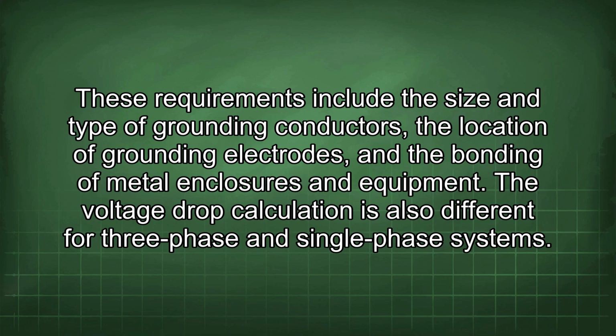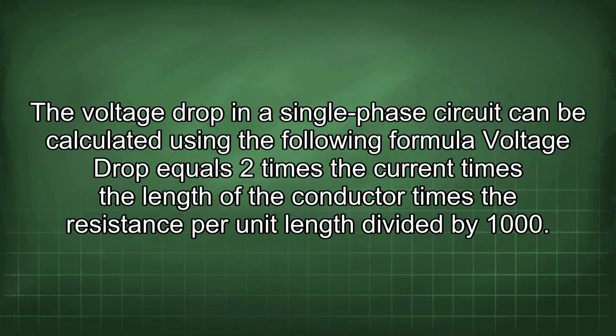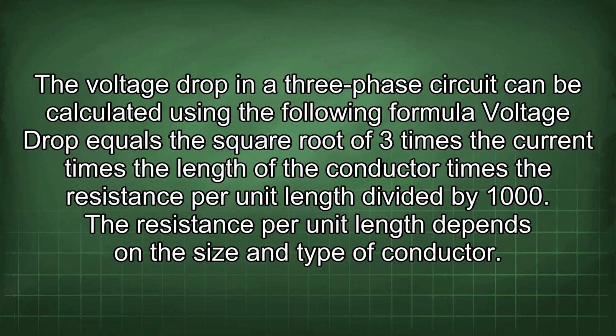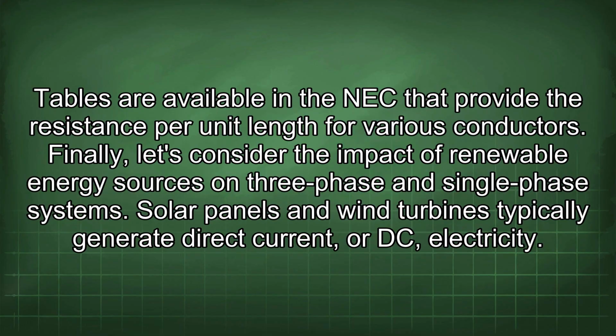The voltage drop calculation is also different for three-phase and single-phase systems. The voltage drop in a single-phase circuit can be calculated using the following formula: voltage drop equals 2 times the current times the length of the conductor times the resistance per unit length divided by 1000. The voltage drop in a three-phase circuit can be calculated using the following formula: voltage drop equals the square root of 3 times the current times the length of the conductor times the resistance per unit length divided by 1000. The resistance per unit length depends on the size and type of conductor. Tables are available in the NEC that provide the resistance per unit length for various conductors.